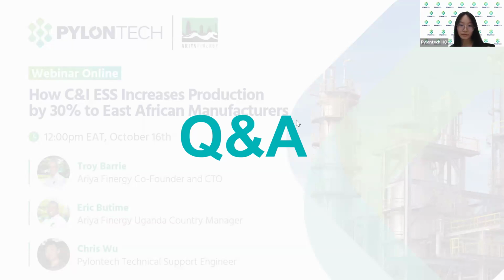When the battery system is connected with the PCS, it will also report the suggested stop voltage to the PCS so the system will not get into over discharge. In case we replace a module, if it has a problem we can replace it and add a new module inside, just making sure the new module has the same voltage level as the old one. After several cycles, all the modules will reach the same capacity level.